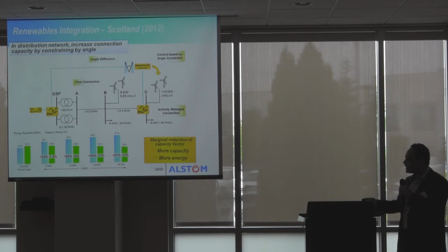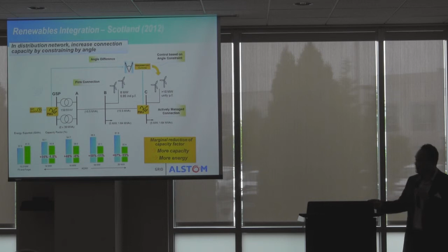PMUs are also used in distribution, and we're doing that in Scotland, to decide when to connect wind farms. The classic approach of fit and forget is really conservative. The nice thing about distribution is we're talking about radial systems, so having just two PMUs, one at the connection point and one at the generator, we can say something about the capacity between the two, the impedance change, and the flows, purely by looking at the angles. Using the angular separation, we can decide when we can push more renewables through there.